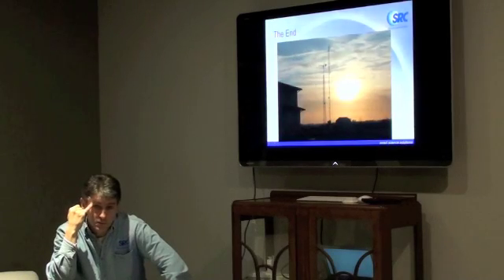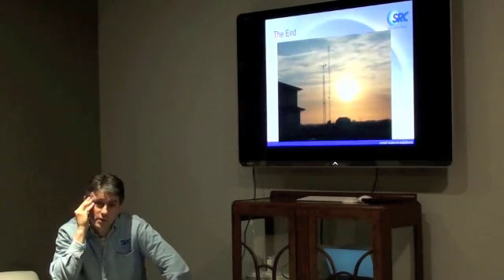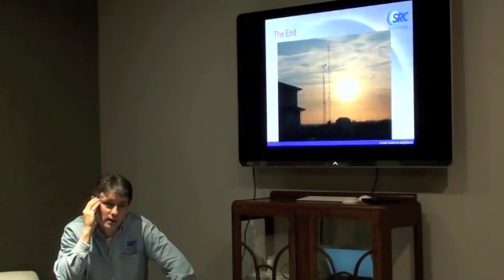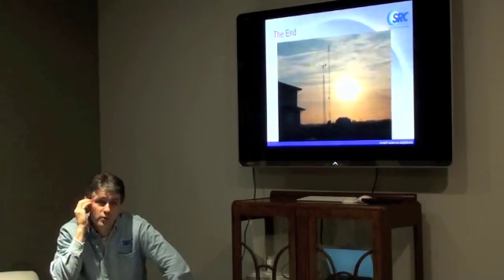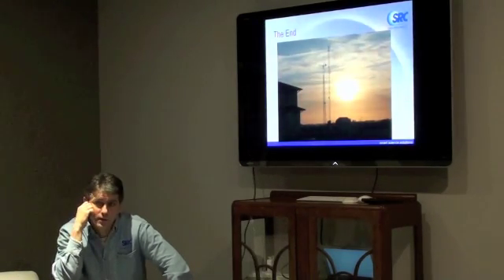Some of these solar thermal systems do have monitors on them, but we're monitoring separately. That was one of the lessons we learned from the Ecoterra house: if you want reliable data, you've got to put a meter in and not necessarily count on getting data from other sources, because they've got different priorities than we have.